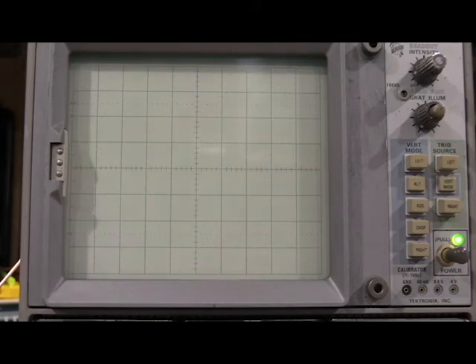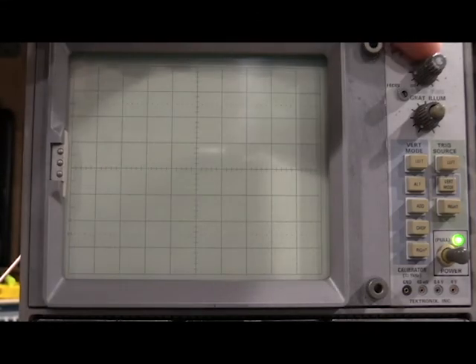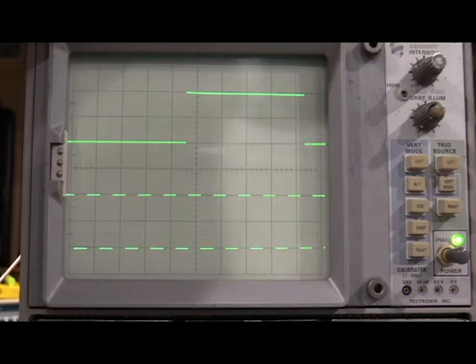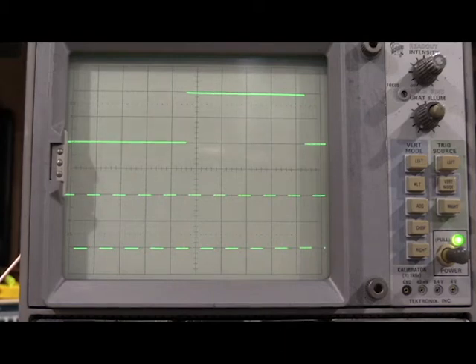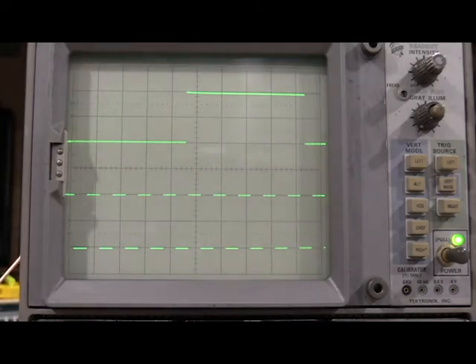Okay, I'm into testing the triggering section of the mainframe. Still on the 7603 mainframe. In this case, I have a 1 kilohertz square wave going into the input on the left vertical, and then I have the calibration test fixture going into the right vertical, 2 square waves. I don't care about what wave shape is at this point because we haven't calibrated the plugins. The only thing this step is looking for is a stable display as the scope is alternating between the 2 trigger inputs. So we have vert mode and alt, and we have trigger source in vert mode, so it's triggering off of both waveforms. So this particular test, everything is passing.